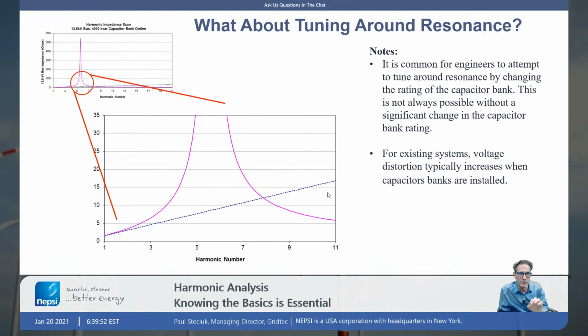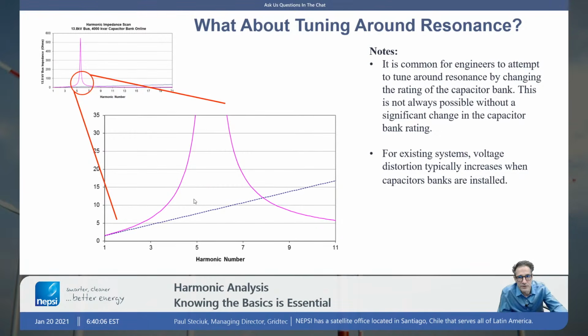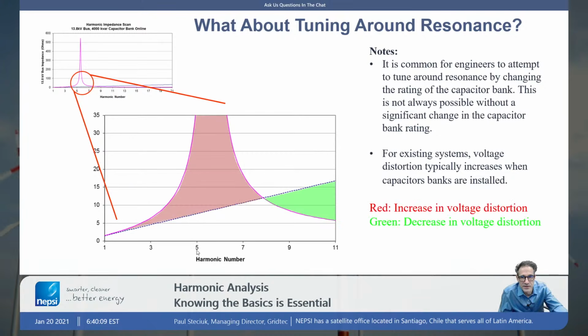You often get a concept where people say, I want to tune around resonance. So we zoomed in on this one. In this case, we zoomed in on that same curve here, and I showed down here. And you can see that in this case, even though my resonance was 5.59, and if somebody was doing some hand calculations using that simple formula, they might say, well, I got 5.59, I'm okay. Or they might say, I'm going to design my system, I'm going to install a capacitor bank that tunes me to the 6. And I'm going to avoid resonance by tuning my cap bank to the 6.